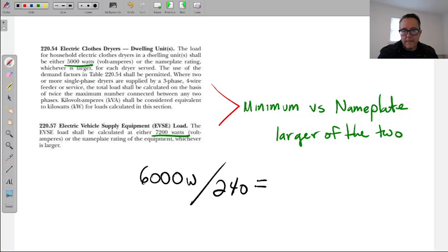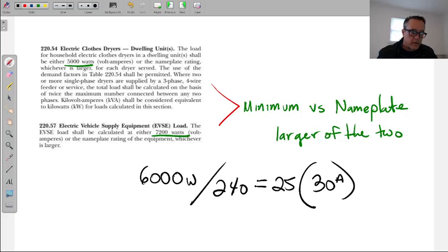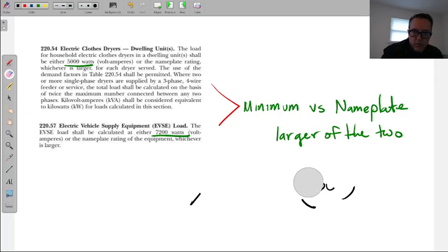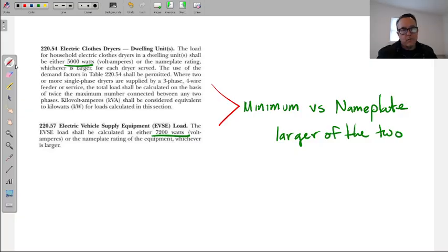Right, and I have what, 25 amps there. I believe the code, don't quote me on this, says we have to have a minimum of 30 amps for this one. So that would work, 30 amps, run number 10 wires. And so when you're doing individual loads for add-ons, this is where, again, Ohm's law, P over E equals I is one of the most used. E times I equals P wattage sometimes, but most of the time, not really. There is going to be an application for that, and it's when you're trying to size transformers.